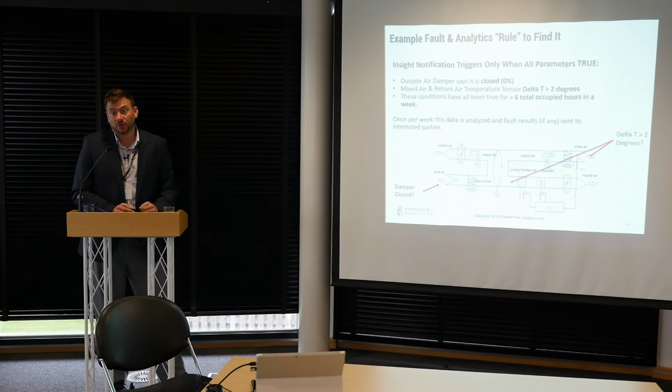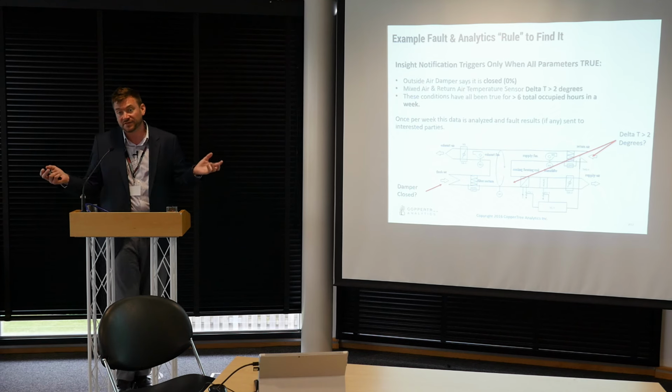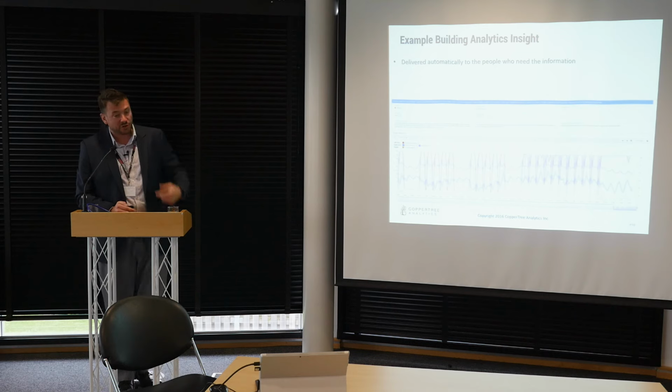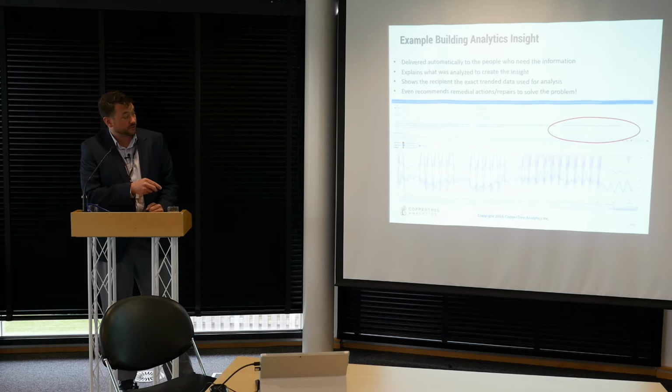So we look every minute, or however often that sample is coming, and we total up the total amount of time in minutes and then hours that delta T is greater than 2 degrees. And if it's in excess of 6 hours, we notify the personnel in the building, okay? What it kicks up, and I'll show you a live demo of this, is an insight notification. I want to differentiate it from alarms, because the difference here is that it's confirmed, it's measured, it's validated much more than an alarm would be. So it not only tells you this is what's happening, here's the data for it, this is what you should do about it. So it really takes a lot of that subjectivity out.